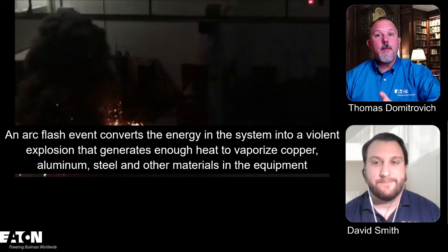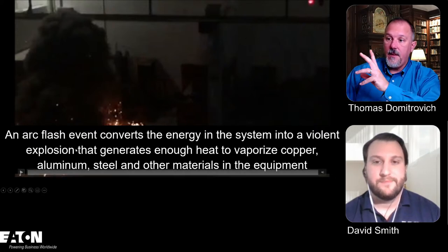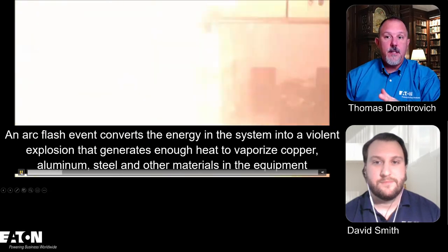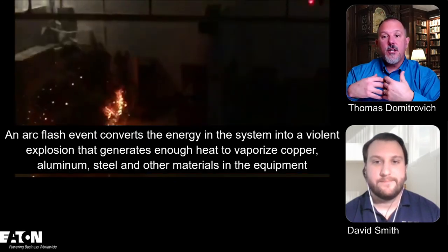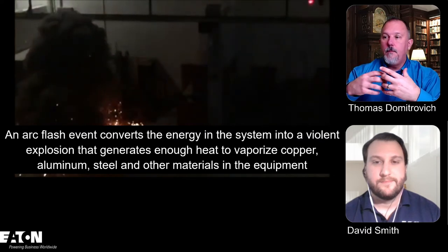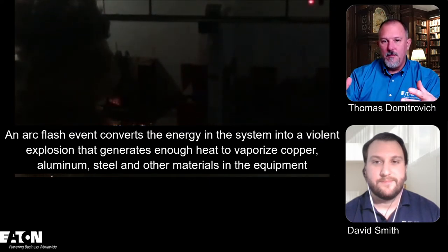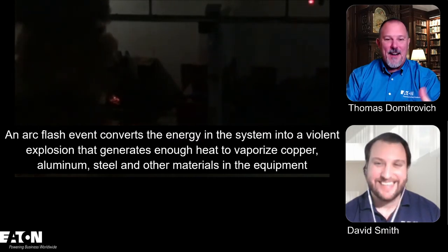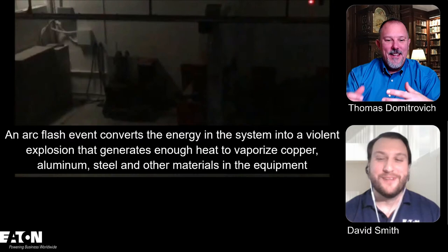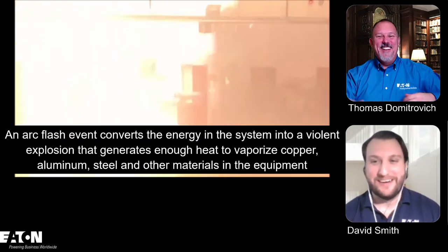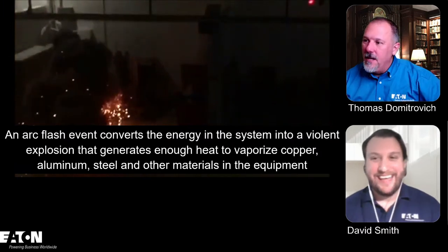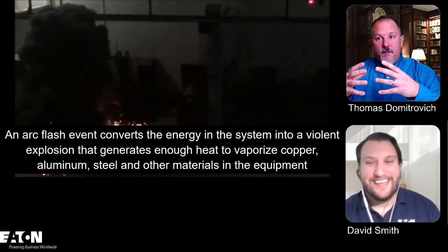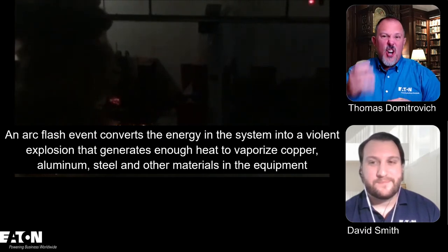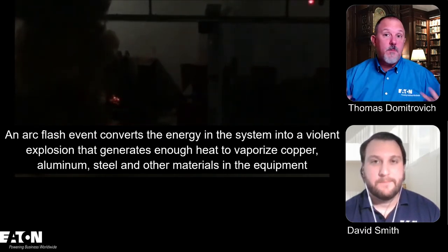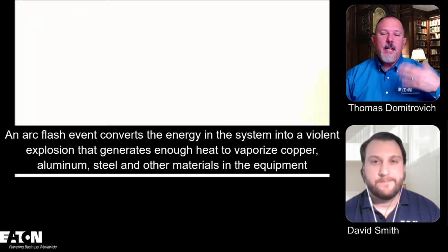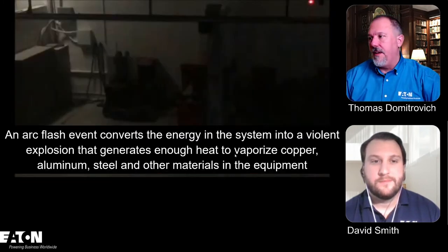Right. And you think about the amount of current that's flowing. This event is an arc flash event. What you're seeing with the light and all that good stuff, that's an arc flowing through the air. The impedance of that plasma plume, I call it a plasma plume, and typically people laugh. I don't know why. I know that you love that word. It's a plasma cloud. Well, but the impedance of that plasma is going to change based upon the amount of copper and steel and what's melted and what's been vaporized. So that changes the signature of the arcing currents and all that jazz.